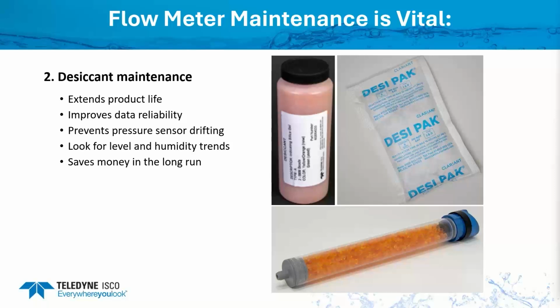It helps improve the data reliability and prevents drifting on your pressure sensor. In a few slides, I'm going to cover using trends, looking at the level, temperature, humidity, and all those things as ways to determine when you need to change your desiccant. As you can see here, the importance of desiccant is to help keep your components and electronics dry. On the inside of your instruments, you may have loose desiccant beads, or you may find that it comes in a desiccant pack, or even possibly a vent tube, depending on what equipment you have.